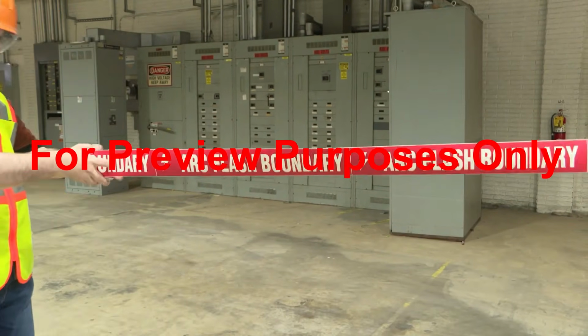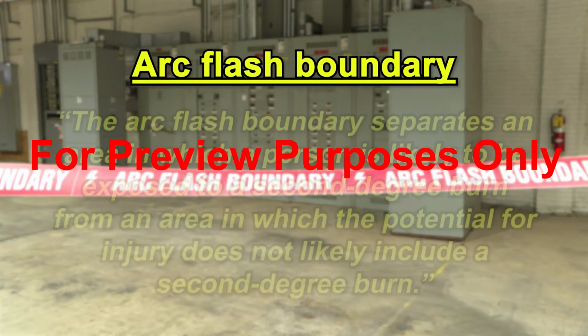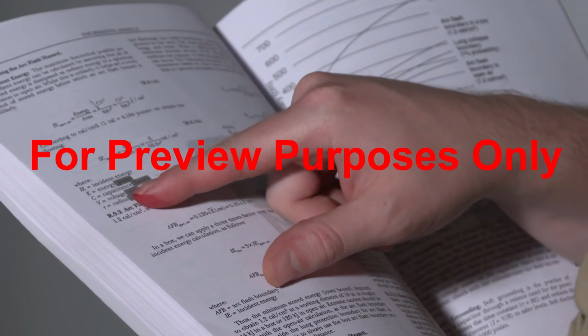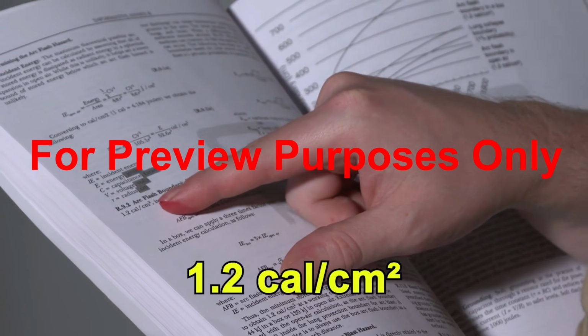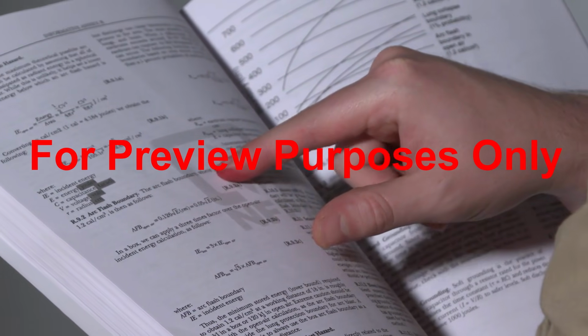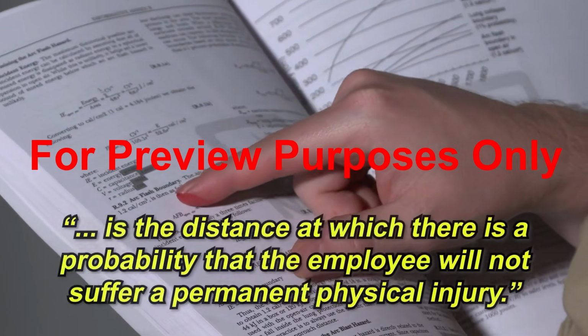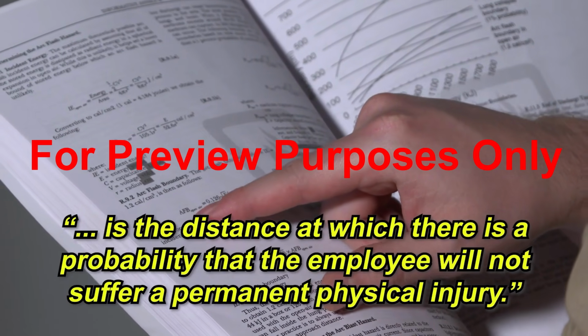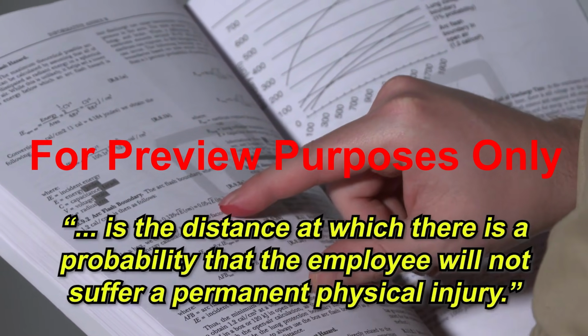The NFPA 70E also stresses the importance of a third boundary, the arc flash boundary, stating the arc flash boundary separates an area in which a person is likely to be exposed to a second-degree burn from an area in which the potential for injury does not likely include a second-degree burn. The standard uses 1.2 calories per square centimeter to determine an arc flash boundary because it is the distance at which there is a probability that the employee will not suffer a permanent physical injury.